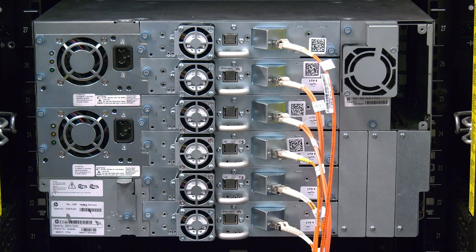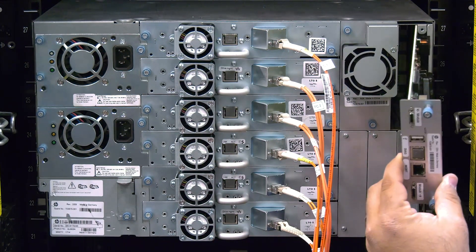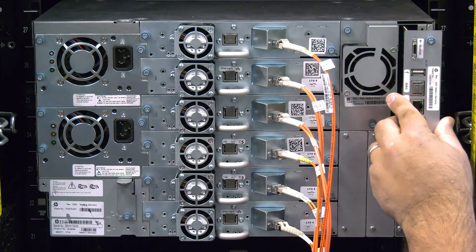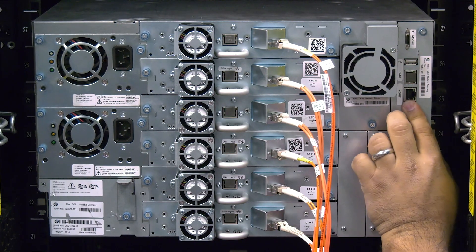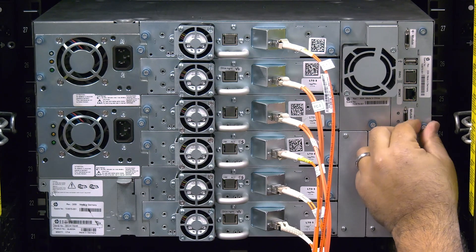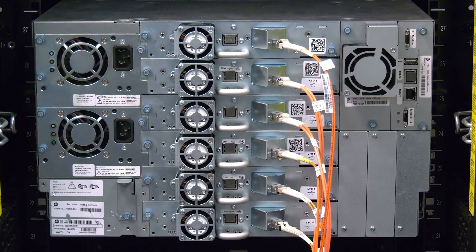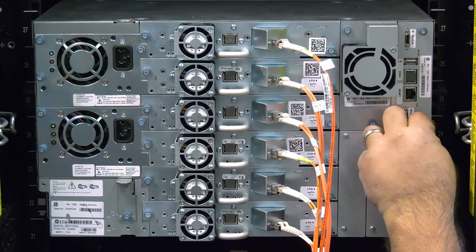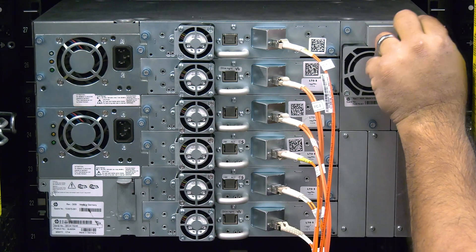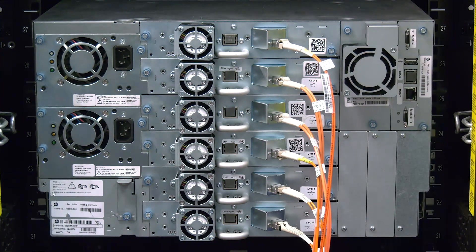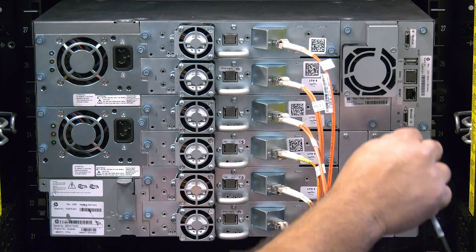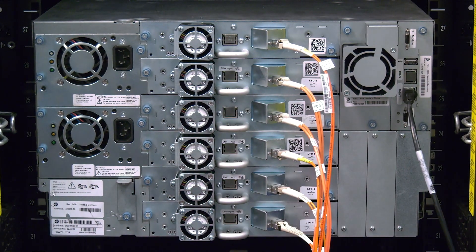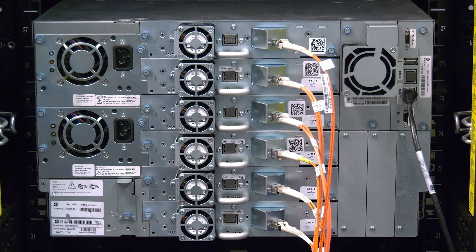Now you can install the replacement control card by lining it up with the guide rails in the control card bay and pushing it in firmly. Once it is fully seated, tighten down the two blue thumb screws and ensure that the card is secure in the library. Then, proceed to reconnect the module interconnect cables and ethernet cable if they were present.